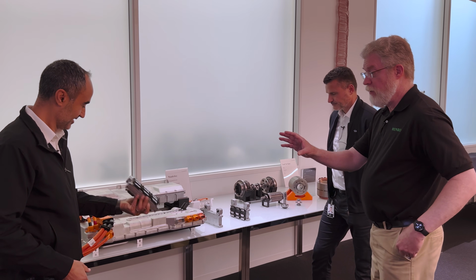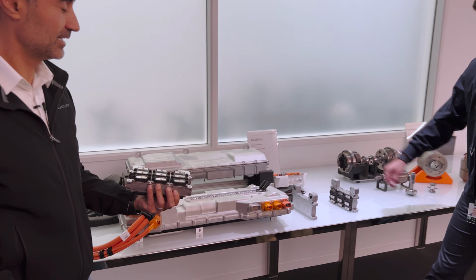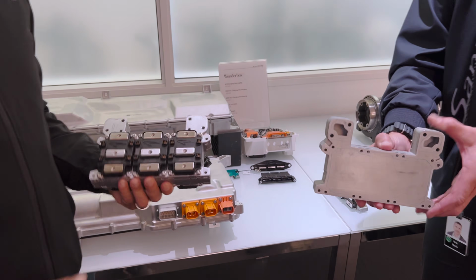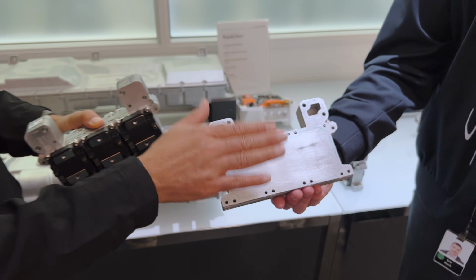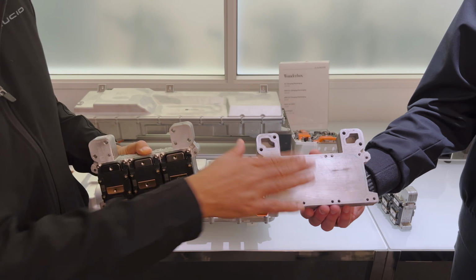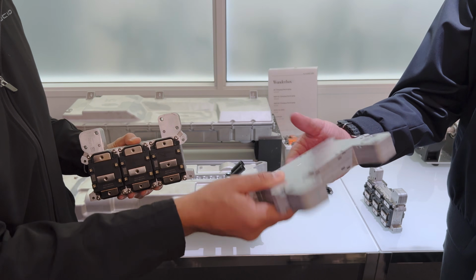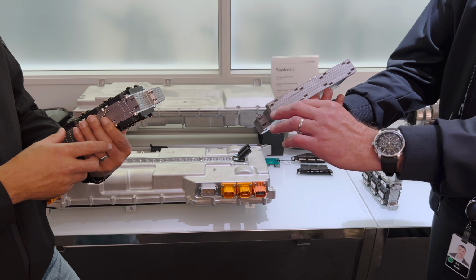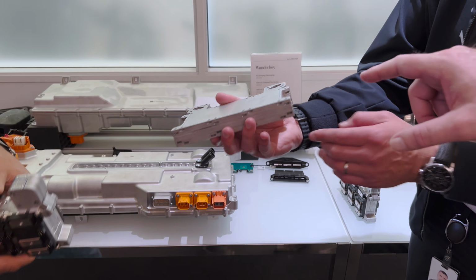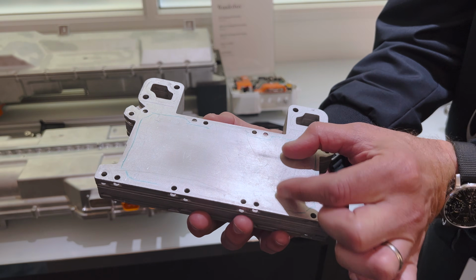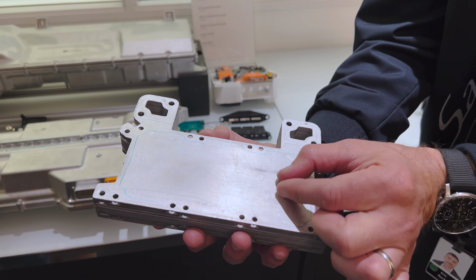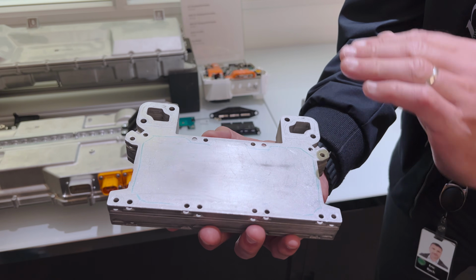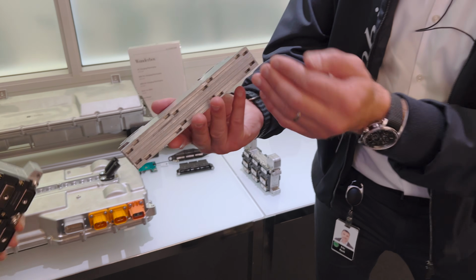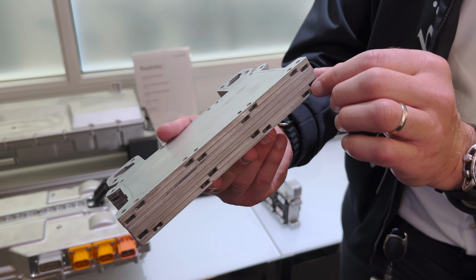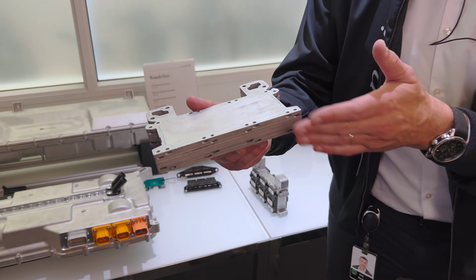This is an incredibly compact heat exchanger for double-sided IGBT and silicon carbide switches. Designed, simulated, manufactured in-house, though sometimes we outsource some of the big technologies. This is 3D flow made with laminated aluminum parts, with parallel coolant flow, so we've got influx and out, but it flows in parallel across all 6 modules underneath the silicon carbide, completely uniformly. It's essentially super cheap, standardized plate-stacking technology, brazed. It's the same heat exchanger technology used in a $10 heat exchanger, the same type of technology.